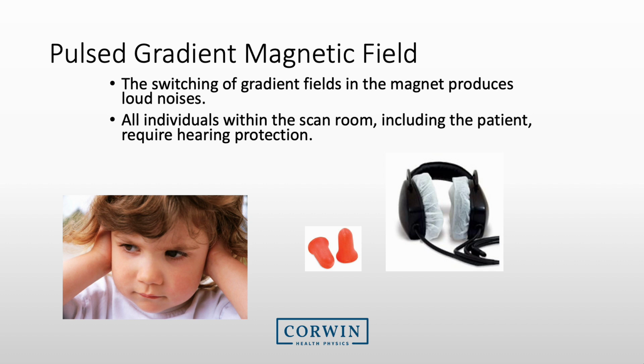The final main hazard associated with the MRI systems is the pulsed gradient magnetic field. This is the loud switching of gradients that occurs only during the exam. Our main concern with these noises is hearing loss, so we recommend that all individuals within the room have hearing protection.